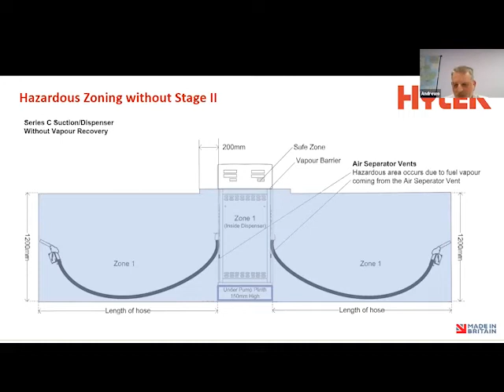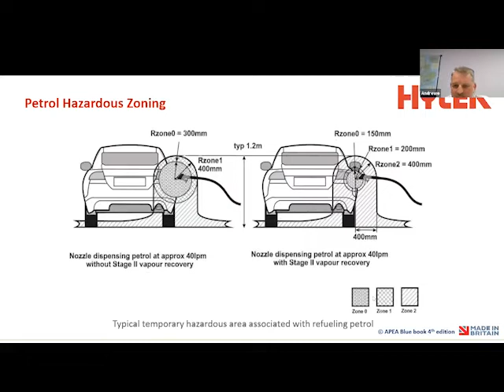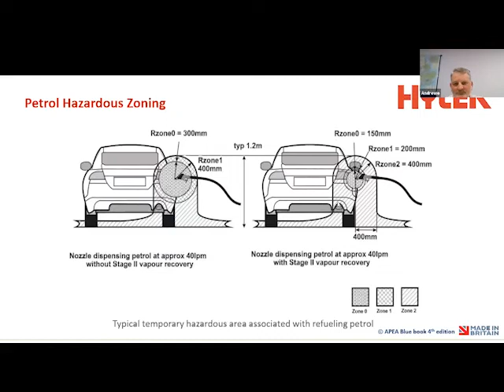If we look at what happens when we implement stage 2 vapour recovery, we can see straight away the zone 0 has been reduced, and we have an increase in zone 2, so that's a less hazardous area, which then goes into a simplified drawing here. We now have a zone 2 area coming away from the pump and to the point of dispensing. So we've been able to control and reduce that hazard.